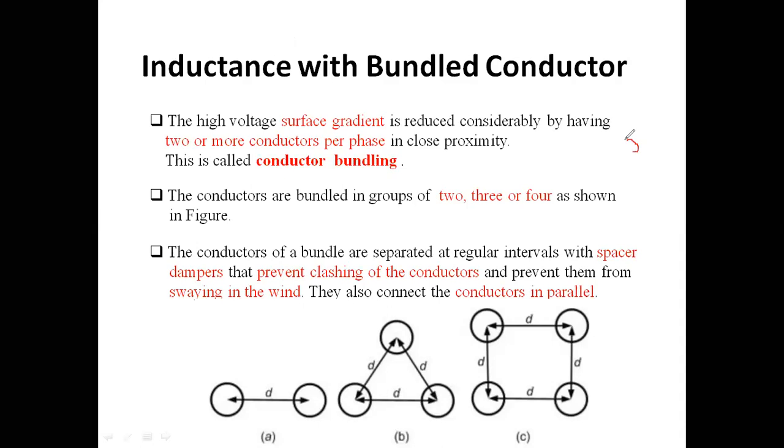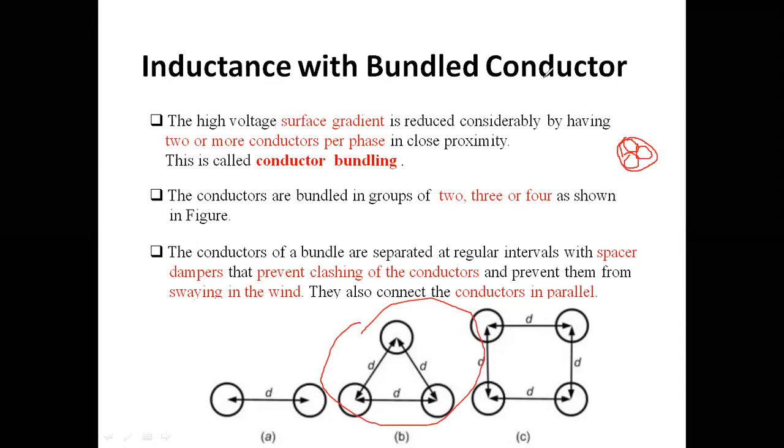Suppose these are your conductors. Instead of this kind of construction, if they collide like this, or they are touching each other, then as a whole they will act as a solid conductor. So again, corona may take place. To avoid this, we use spacer dampers to separate them at regular intervals.